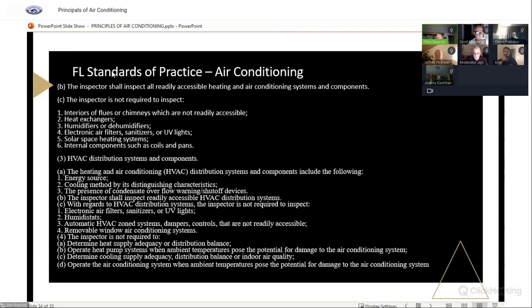Stan, can I ask you a question? Yes. In an attic space with the flex ductwork or even just rigid ductwork, sometimes I'll see the people go in there after that's been installed. Say there's fiberglass insulation on the floor, but then they'll go in and they'll blow in blown insulation. That's okay to cover that ductwork. And what I see a lot of times is sometimes part of the ductwork's exposed, some is not. So I mean, insulation, if you're in an attic and you're blowing cold air through an attic and the attic's 110 degrees, the insulation is not hurting the process. But I want to see the ductwork, because that flex ductwork, that breaks down. It could just start to shear and have holes in it, and you need to see it, in my opinion.